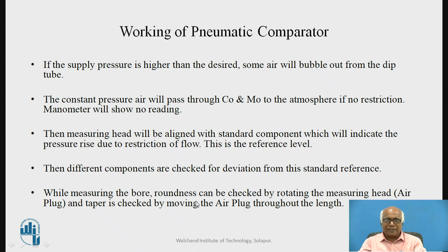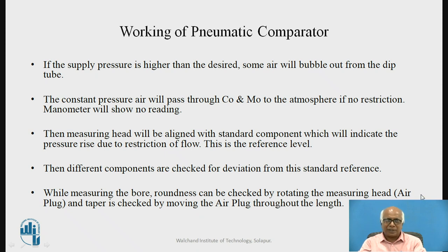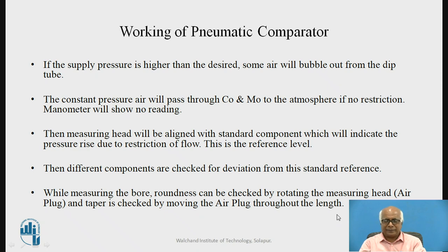While measuring the bore, roundness can also be checked by rotating the measuring head or air plug, and taper is checked by moving the air plug through the length.